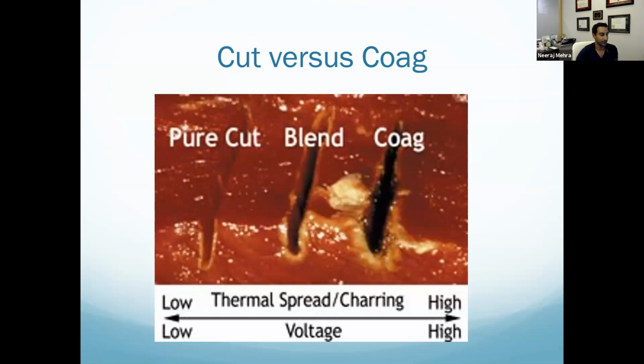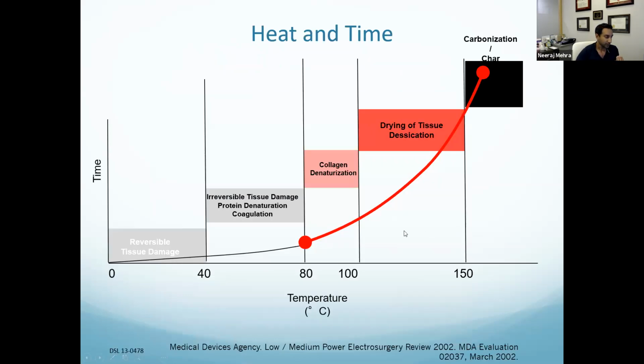Now those are the modes. What concerns us is how it affects the tissue, and we'll get to this. So if you have a setting, the main thing that we get when you use a cut mode versus a coag mode is char. And this is why. So you think about why we're using electrosurgical energy. When you have electrons and those electrons encounter resistance, that generates heat, and heat results in tissue damage over time. So if you heat up something slowly in the early phase, you get tissue damage, denaturation, and then eventually the collagen denatures. If you heat it up even more, the tissue starts to dry out, and if you cook it really hot, it's going to char.